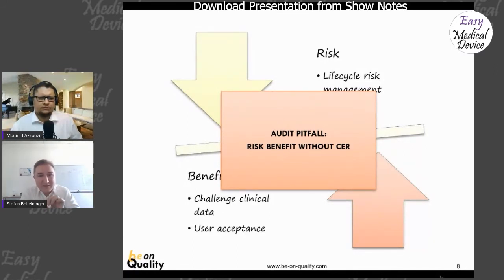If you have different applicational parts, you have different risk benefits. So you have to take each feature of your device, and for each feature, if they are not connected specifically, you have to evaluate the risk benefit for each of them and tell why this is fine or why this is not working correctly.